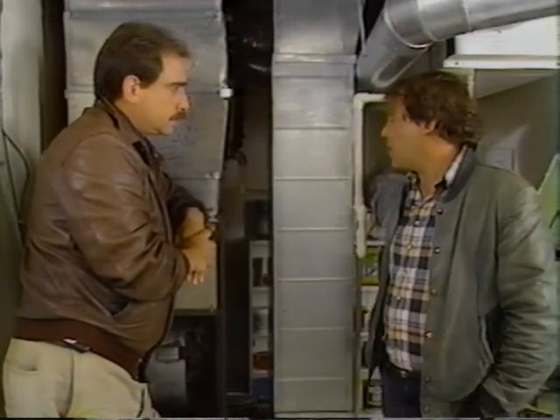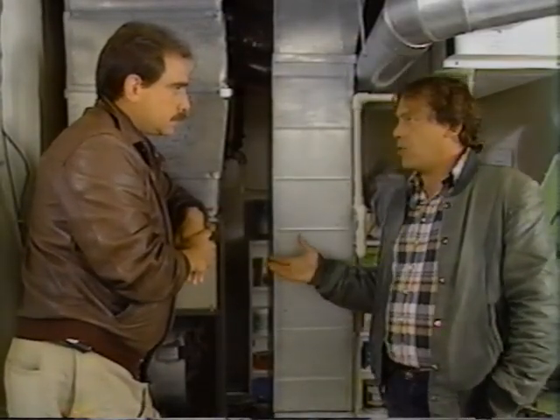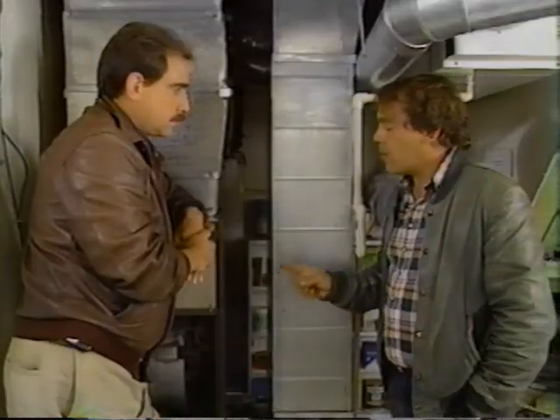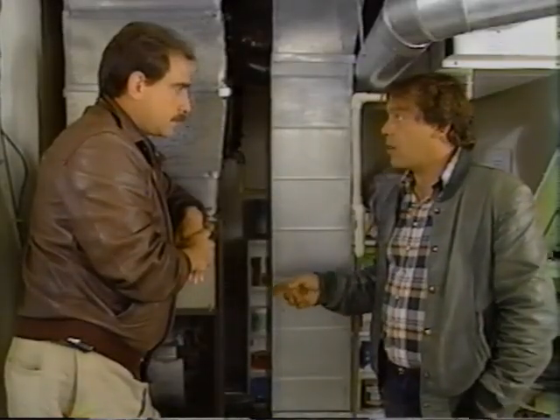Well, if you're using this ductwork to take over the job of delivering fresh air, do you have to run that furnace fan and burn up energy all year round? It's desirable to run the fan in continuous operation, and there is a price that has to be paid for that.